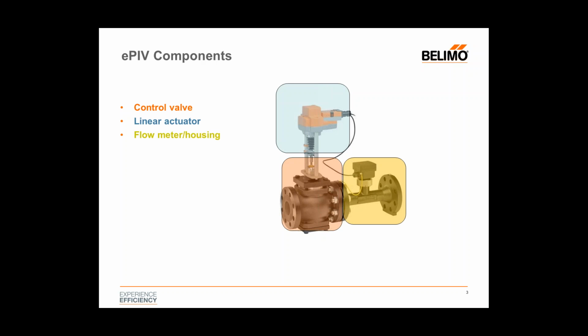We have the flow meter and the flow housing. The flow meter itself is an electromagnetic flow sensor, a very high quality flow sensor that we've been using in these assemblies since 2009 when we initially launched the ANSI 125 versions, and is coupled together with the flow housing. Those together require a 5 times the DN size inlet run to remove turbulence, which is very typical with flow meter installations, to create a laminar flow so we have stable flow measurement across the assembly. So that covers the components of the ePIV.